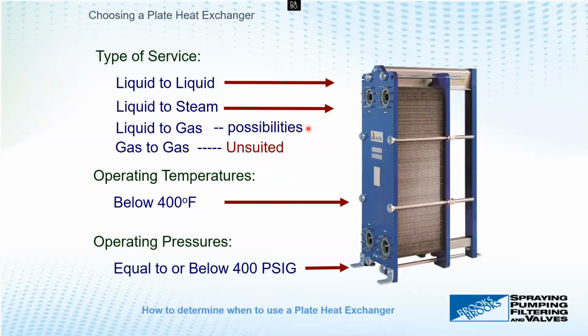And then to multiply that risk up, gas to gas is really unsuited for plate and frame heat exchangers. So liquid to liquid, really good. You've got some steam, some kind of vapors, to a limited degree for sure. And then as we get into more gases and then gas to gas, plate and frame heat exchangers are not very well suited to that. So liquid to liquid is really where they like to live.